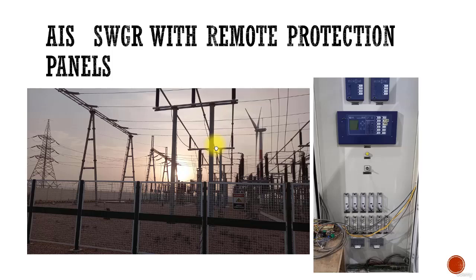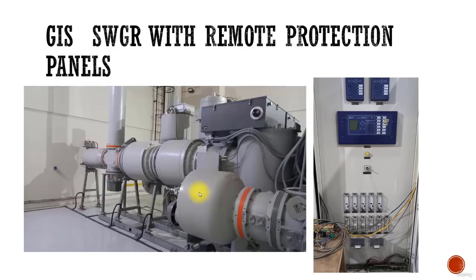If you see an AIS, air insulated switchgear, you can see this is an example of AIS, that is air insulated switchgear. So in the AIS you can see the switchgear is separately installed and the protection devices are separately installed, and these are in the relay room. So this is a very expensive system, but this becomes feasible when the voltages are increased. So you can see this example of GIS. So this is the gas insulated switchgear. The size is now reduced, but still you need a separate protection panel in that.